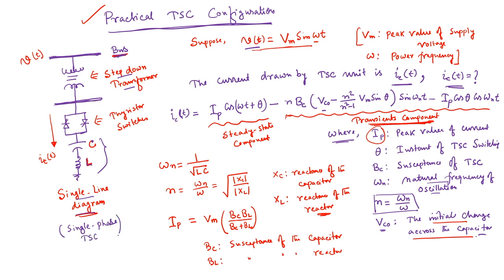We will discuss the three-phase TSC, but before that, we will discuss some practical problems in operating this TSC. One problem already discussed in the last lecture is that when this TSC unit is brought into service, the current drawn by this capacitor consists of two terms: one is the steady-state component, and another is the transient component. The transient component makes the initial current during turn-on very high.